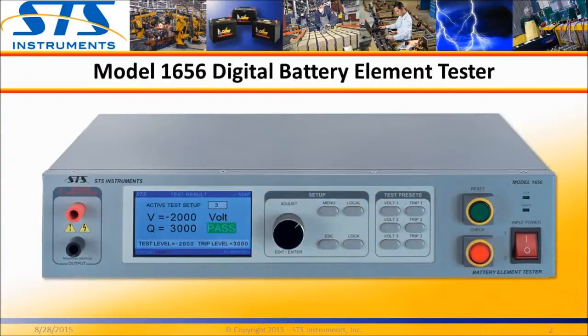This image shows the front panel of the 1656. From the large color LCD display, it is immediately obvious that this is a more modern look than the old 1652, which used two 7-segment LED displays. Some of the old testers' controls carry over, however, such as the reset and check buttons. There's also still a shuttle knob, but in the 1656 application, the shuttle is not only used to adjust the test voltage level, but also to scroll through menus and select parameters and options. We'll go over each control in a minute, but first let's look at some of the benefits that this new digital tester offers.